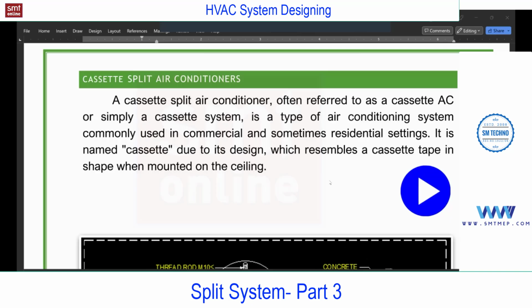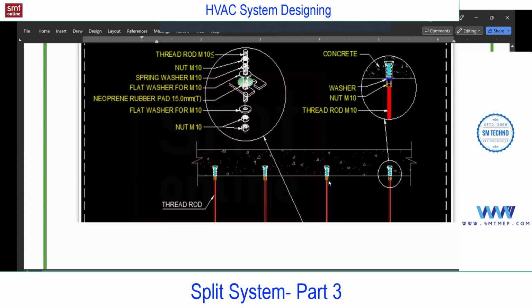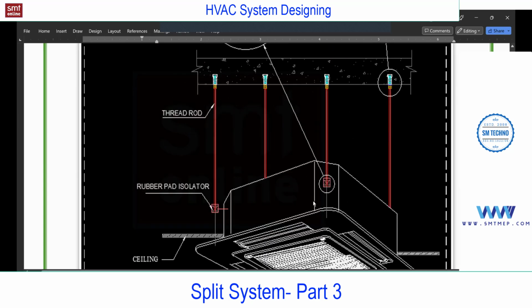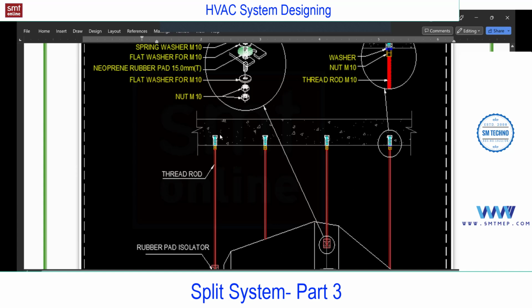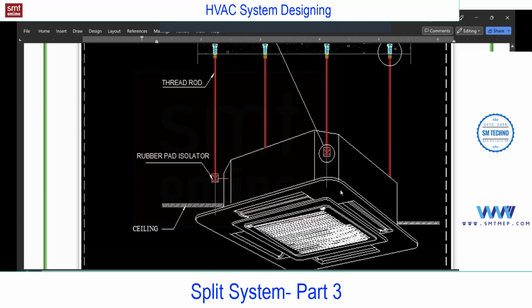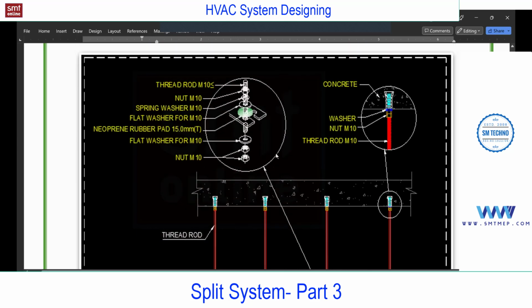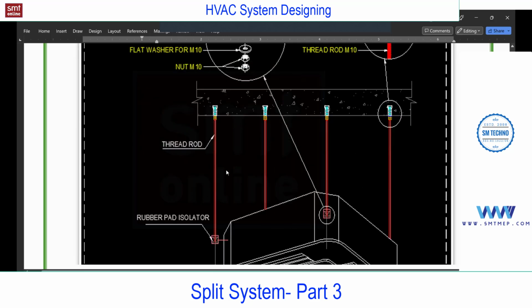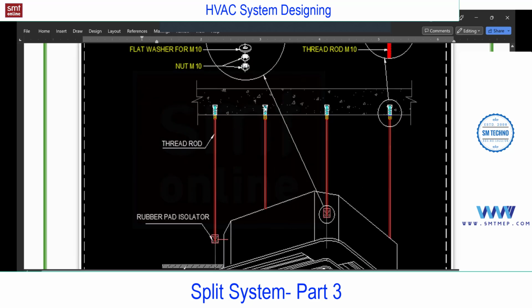Rest of the concept is same as split. Again, this will connect to the outdoor with the suction line, liquid line, with the insulation cabling, same as the high wall. Can you see here one detailed drawing for installation? This is the installation for indoor unit, and these are all anchor fasteners, which is used to connect this full threaded rod. And this full threaded rod is connected to the indoor unit, and in between you'll find the isolators or a rubber, which is used to reduce the vibration from the unit. So these rods are full thread rods, and these are anchor fasteners.